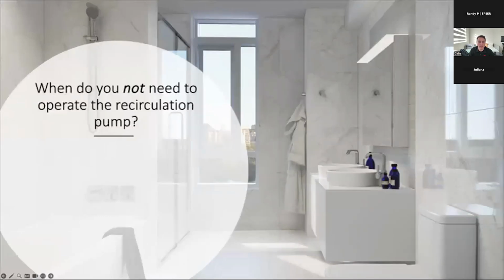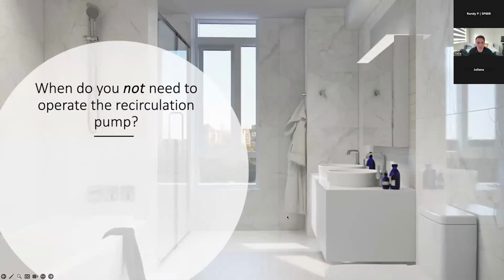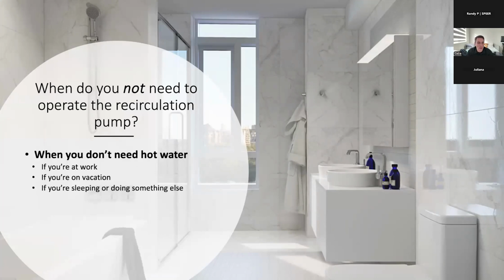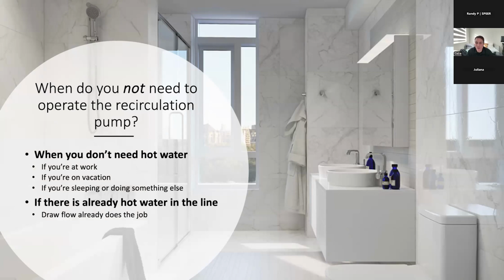Let's see. I'm going to do this slide and I see some questions, so I'll get to that right after this. When do you not need to operate the pump? Well, if you don't need hot water. So if you're not at home, maybe you're at work, maybe you're on vacation, or maybe you're at home and you're sleeping or watching TV or doing something else other than using hot water, that pump shouldn't be running. And also, if there's already hot water in the line, so maybe someone just got out of the shower and your hot water line is now primed, a well-insulated pipe is going to stay hot for a good 15 minutes, right? So the pump no longer needs to run.